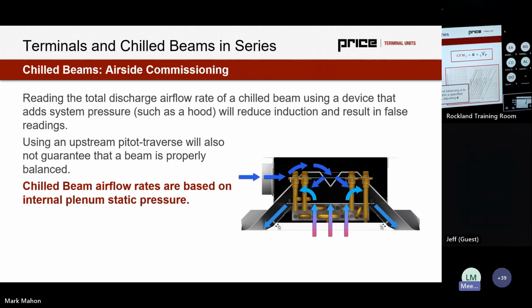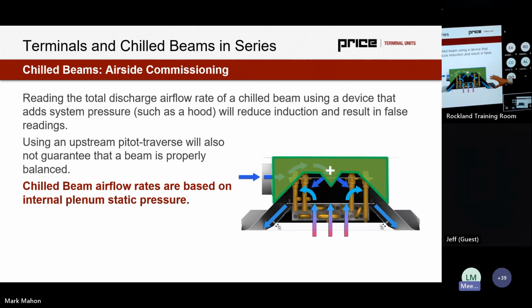We're good? Great. Okay. Now, when we compare this to airside commissioning and airflow measurement and control in a chilled beam, the reality is a chilled beam is not measuring, nor is it controlling airflow, right? It is a downstream endpoint to the ducted system. We need to balance the system to make sure that we get the right pressure in the back pan of the beam, so we have the right airflow delivery out of the discharge of the beam as well. And the way that we do this is by essentially getting a specific static pressure within the back pan of this beam. And there's a few things that means.